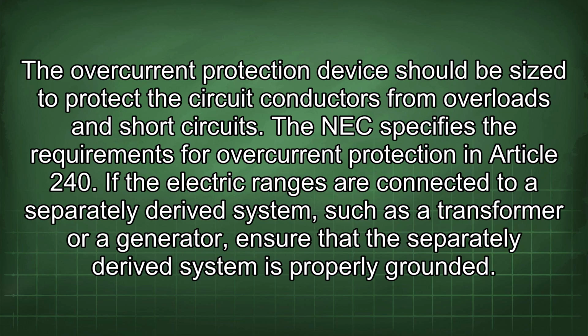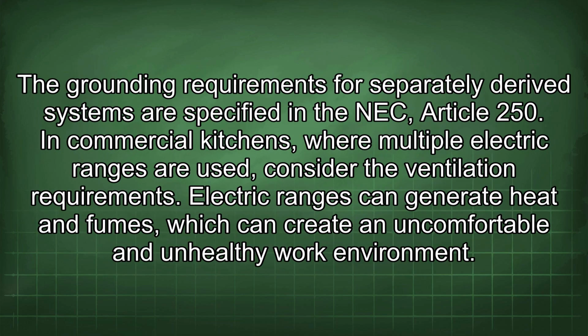If the electric ranges are connected to a separately derived system, such as a transformer or generator, ensure that the separately derived system is properly grounded. The grounding requirements for separately derived systems are specified in the NEC Article 250.